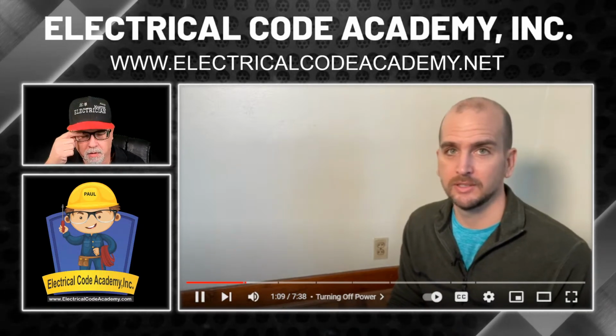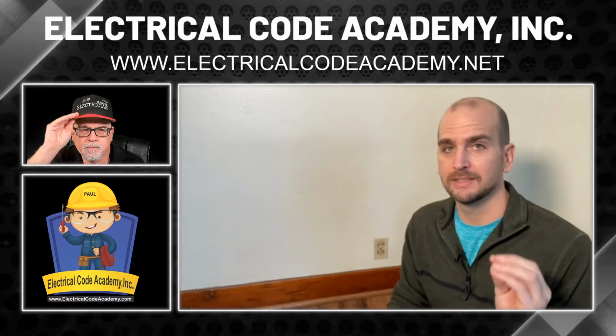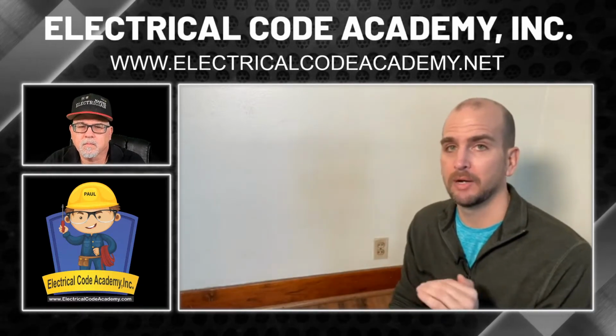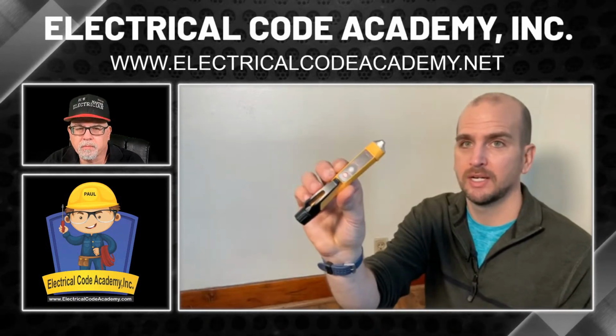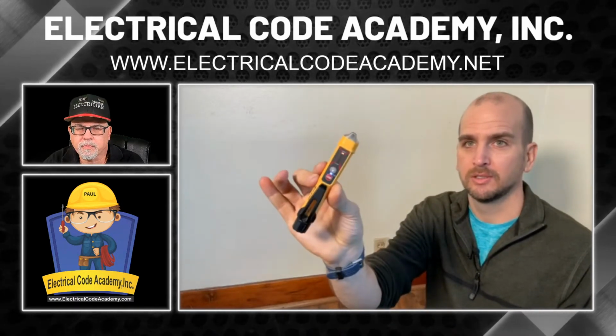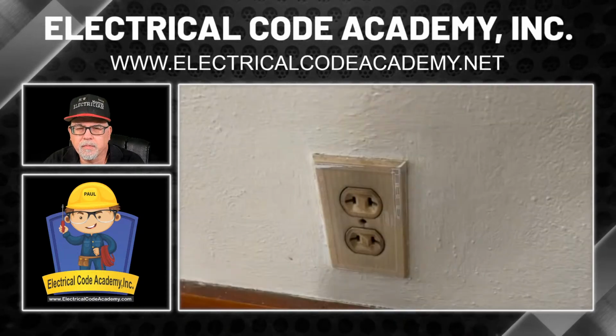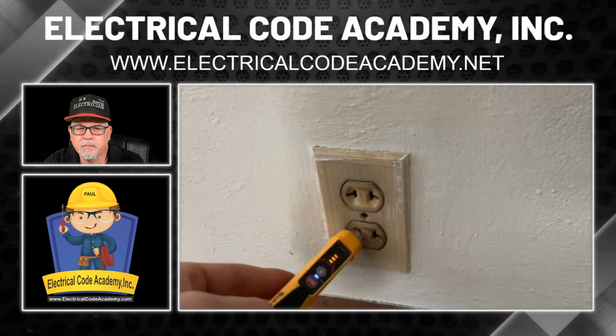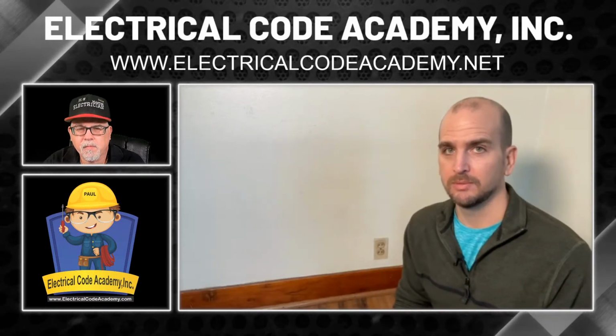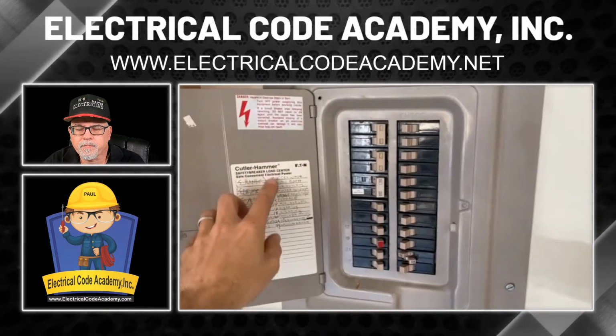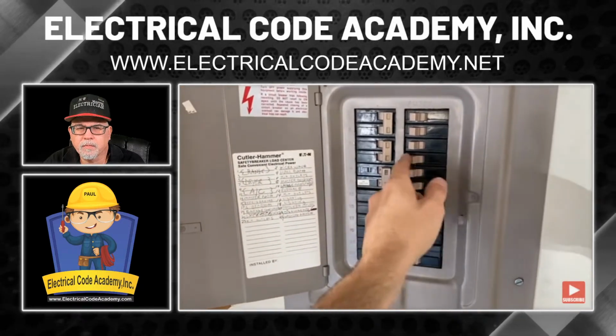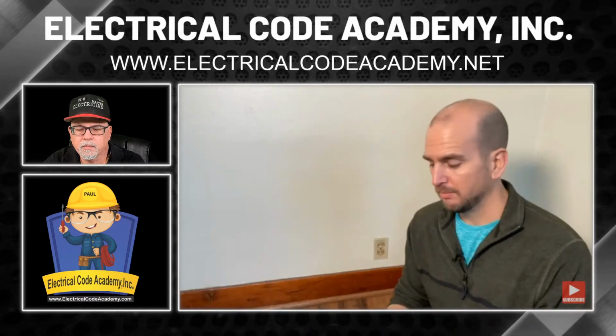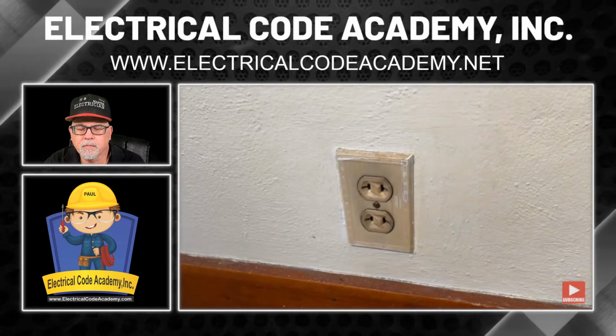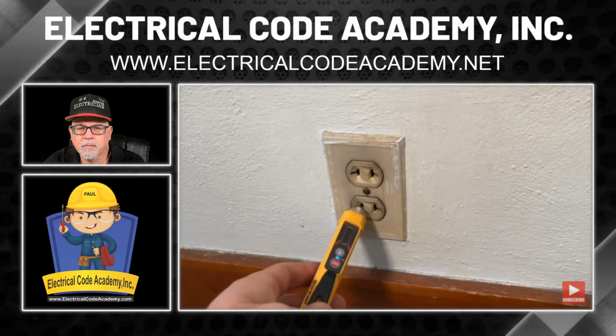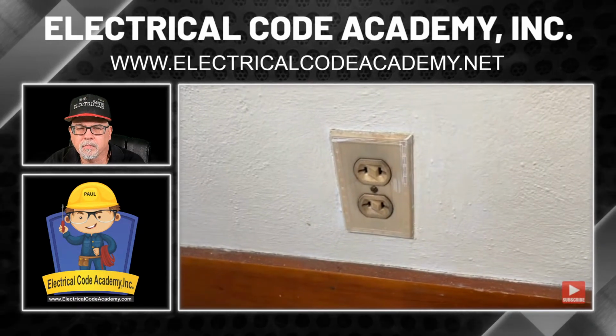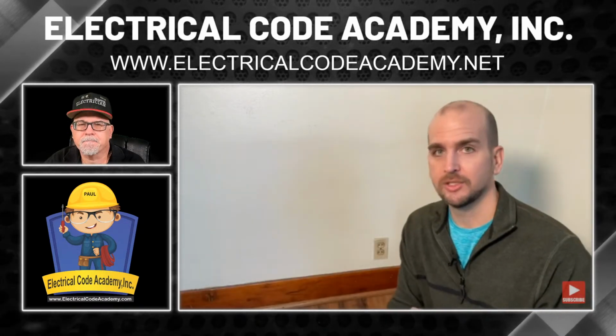So the way we start off any of these electrical projects is to make sure we can safely work on this receptacle and there's no power going to that. To do that, I'm going to use a non-contact voltage tester. I'm going to turn it on and I'm going to test this receptacle to know that my voltage tester is working and power is still going to this receptacle. Once I've confirmed that, then I'll go hit my breaker to turn off power to this circuit. Then I'll come back in, and with the same voltage tester, I will test it again, confirming there is no power going to this receptacle. And once you do that, now we're ready to install the GFCI outlet.